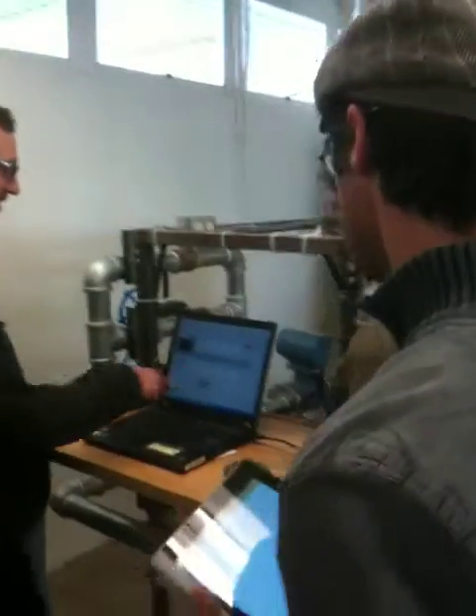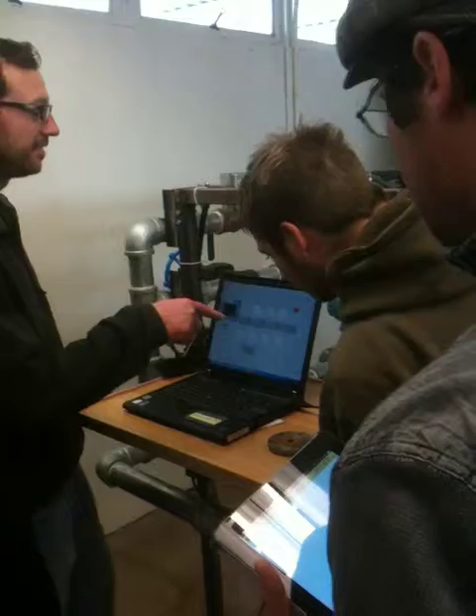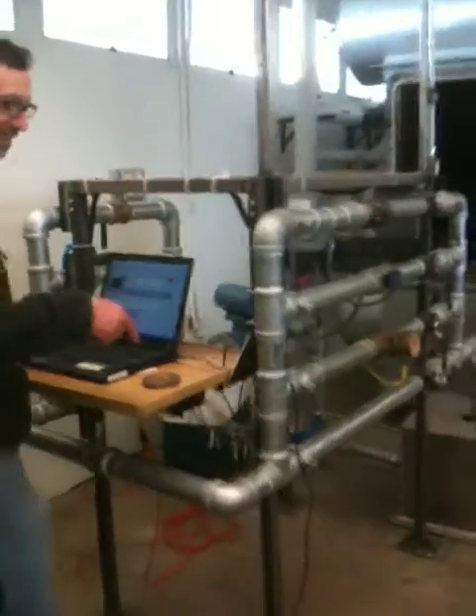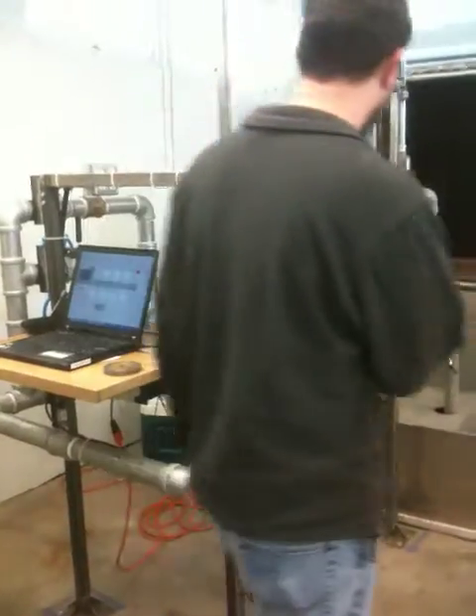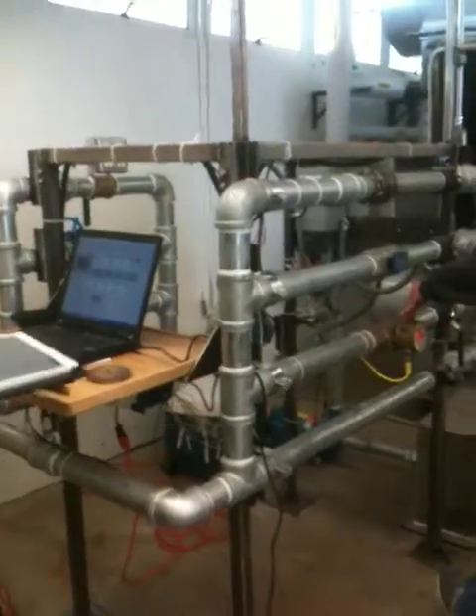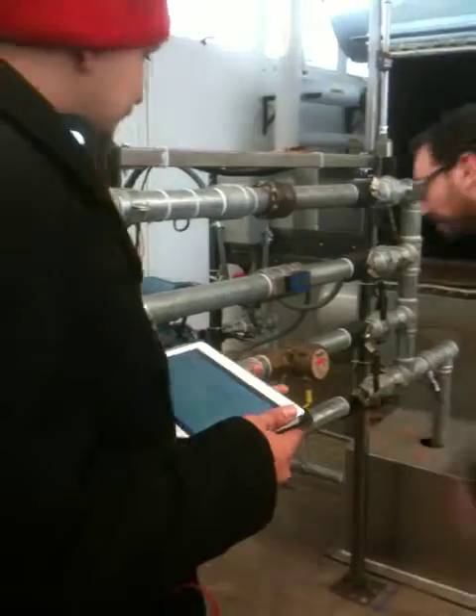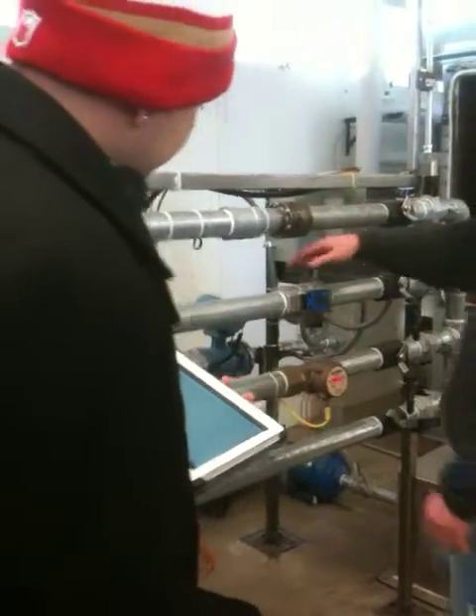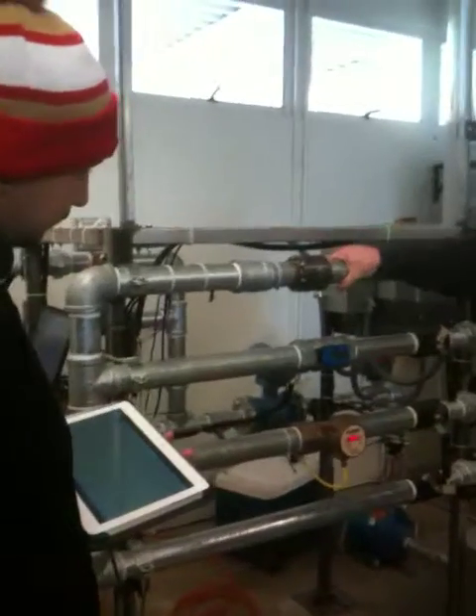The things you can look at. So you'll have flow rate overall, and then you'll also have the pressure difference across, from that pressure transducer to this pressure transducer. So you'll have that one, the very bottom. Then, flow comes over here. You got 3 flow meters. This is the vortex shedding flow meter. This is a turbine flow meter. This is an orifice plate.